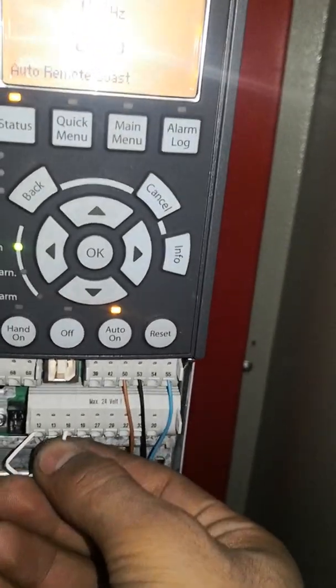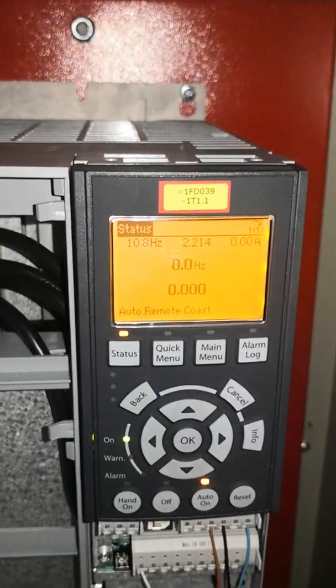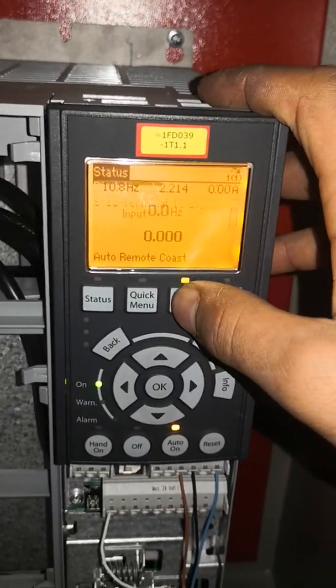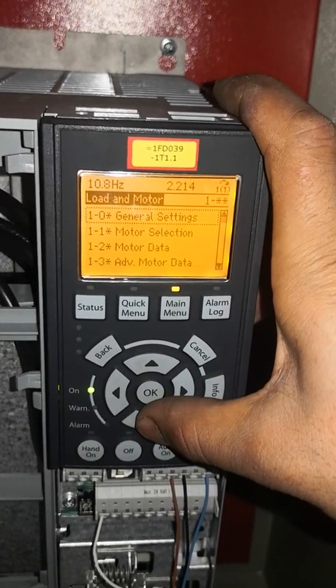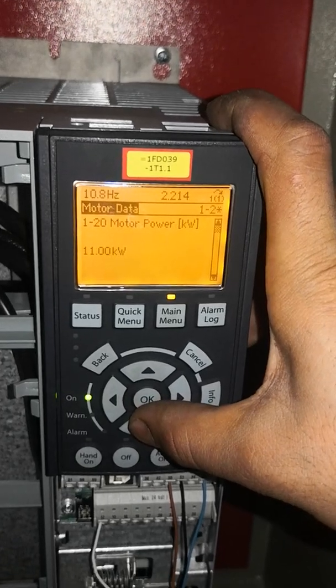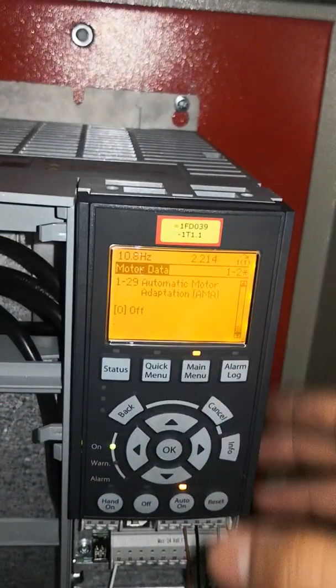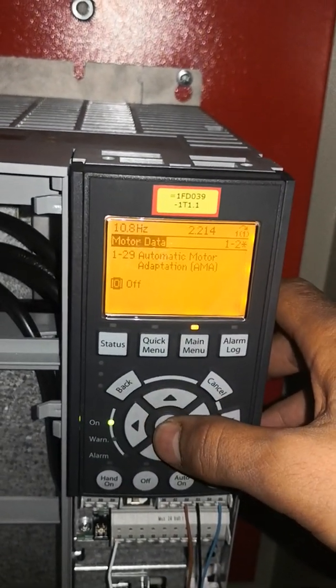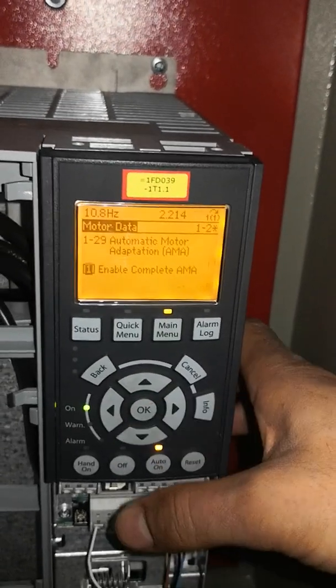The motor is still not starting when I push terminal 18. To fix this, go to the main menu, then Motor and Load, then Motor Data, and come down to parameter number 129 — the Automatic Motor Adaptation (AMA) option, which is currently off.